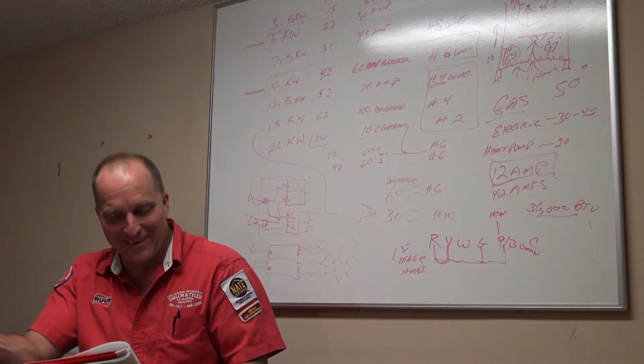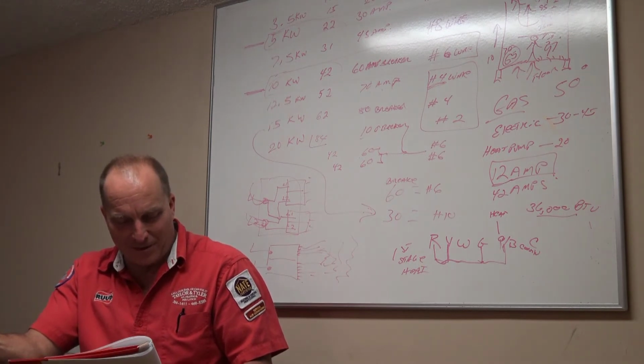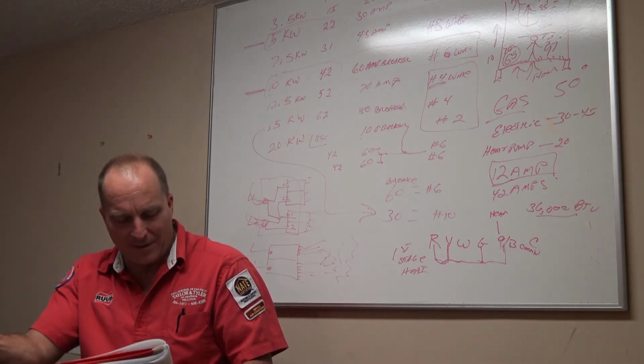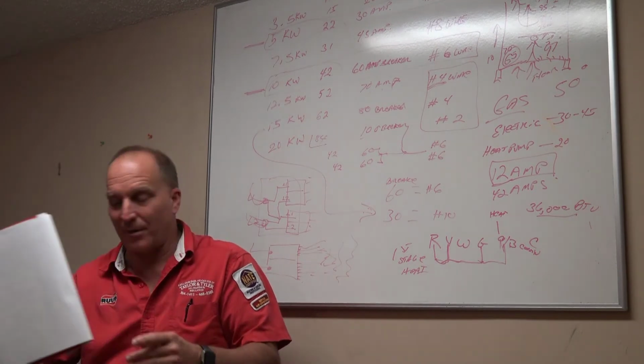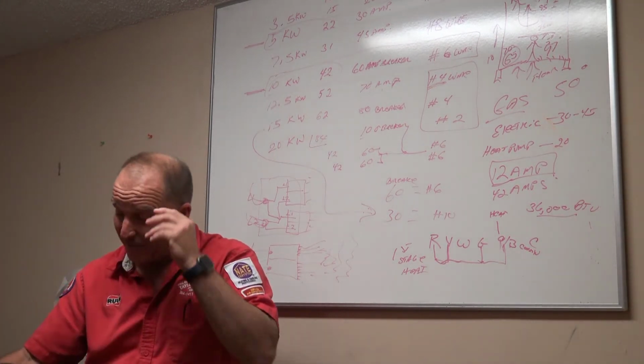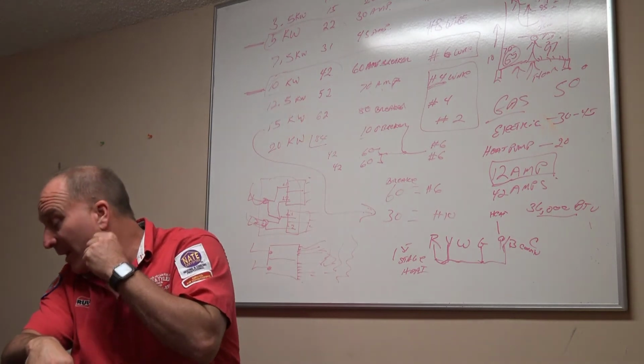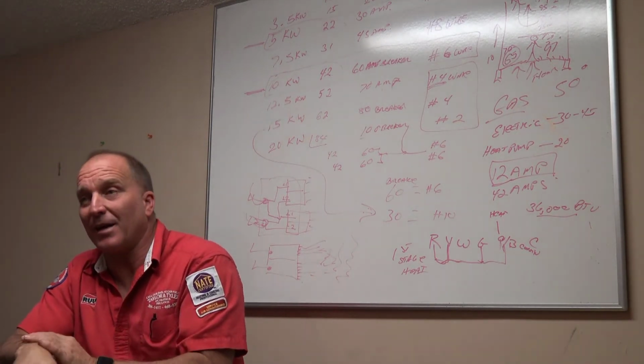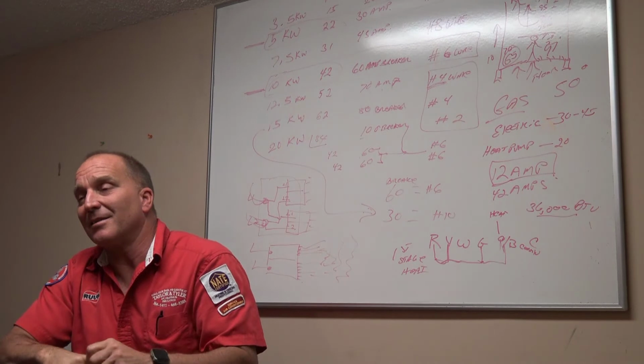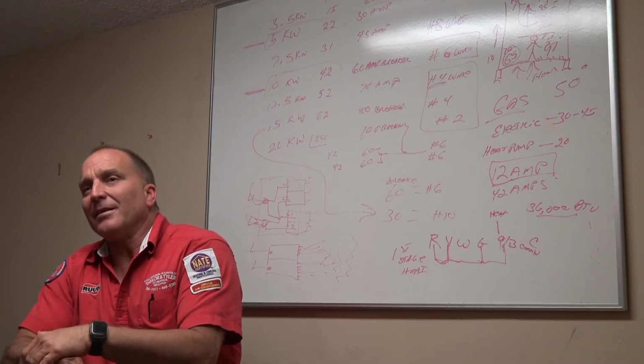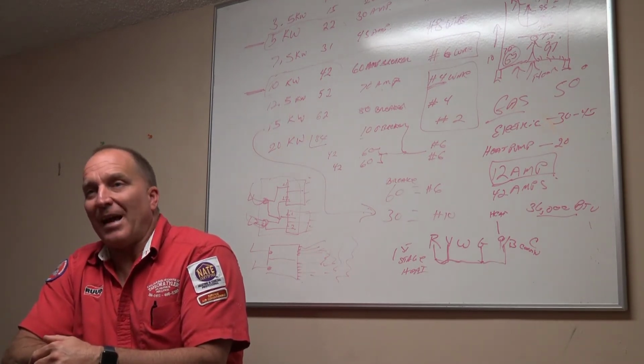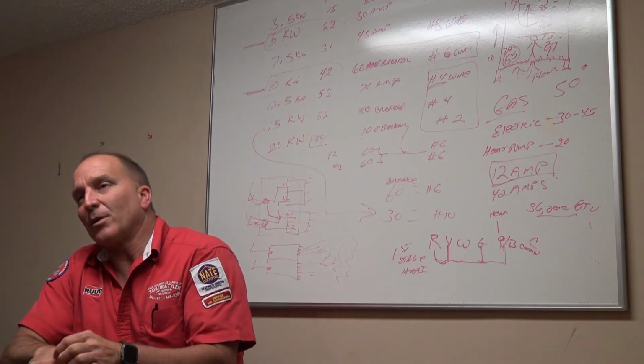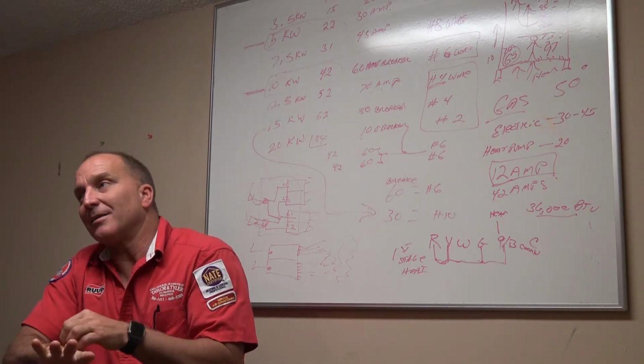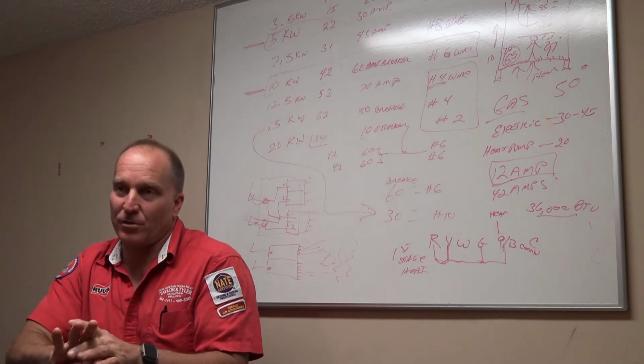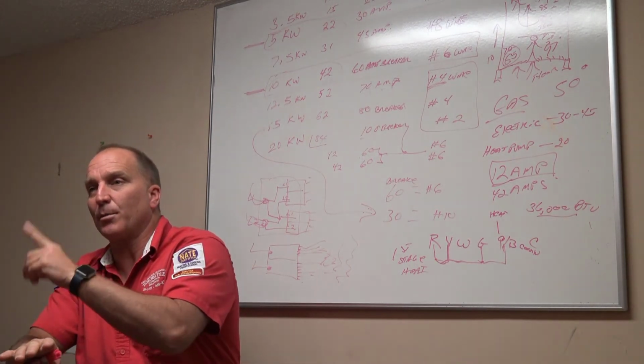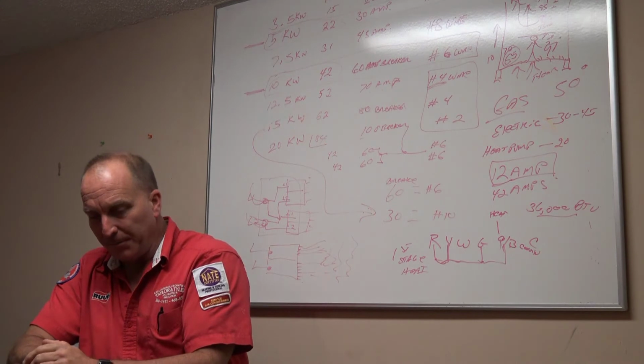Where are we at now, man? Low voltage. We just did low voltage, didn't we? Yep. All right, now we're on heat anticipators. What is a heat anticipator, guys? Which we went over in the last video. A heat anticipator on an electric heat system does the same thing it does for a gas heating system. On a gas heating system, you set the heat anticipator by the amperage of the gas valve. With an electric heat system, you're setting the heat anticipator by the amperage of the heat sequencer. So you have to wait till all heat sequencers are pulled in to set the heat anticipator.